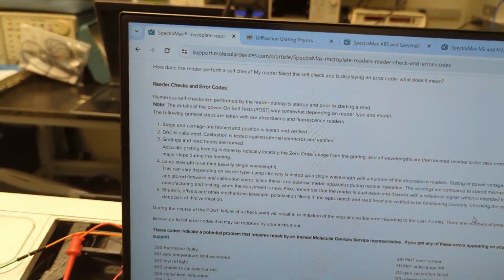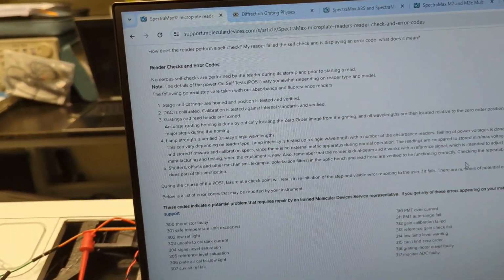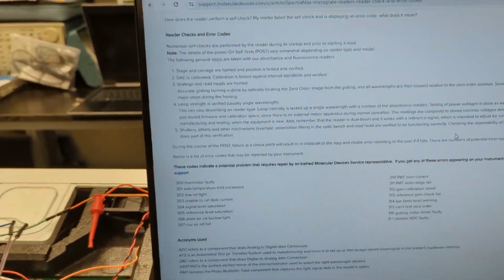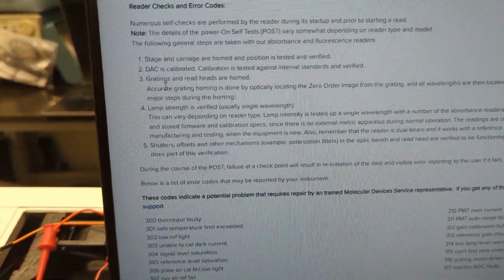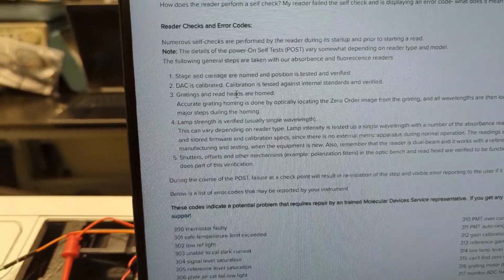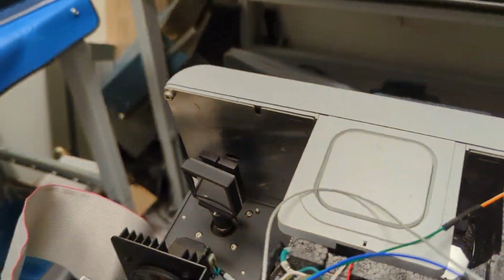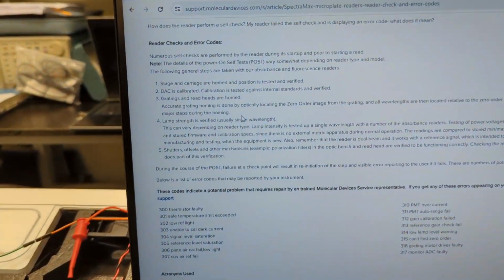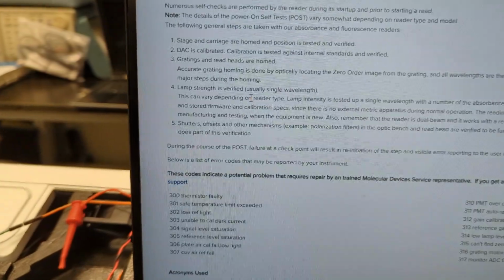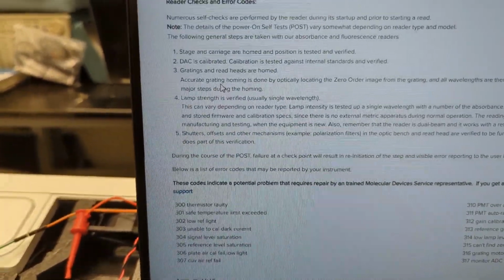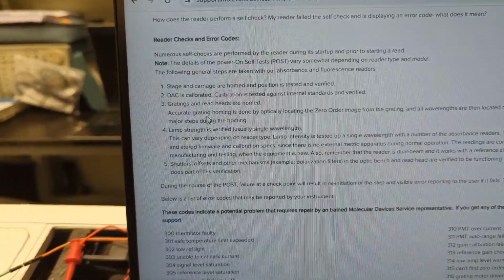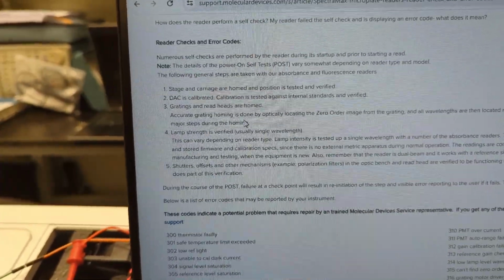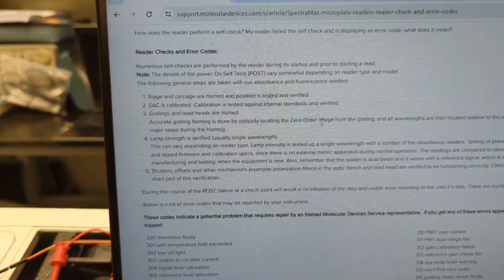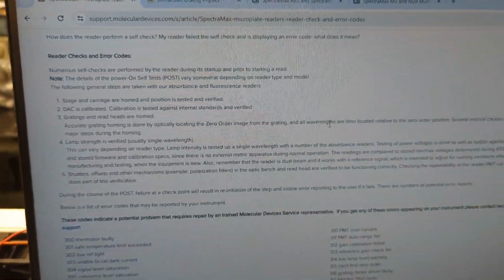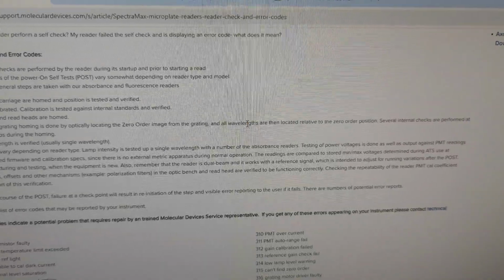Sorry about that. That plate carriage, the drawer will open, it'll close, and then it says the DAC is calibrated, gratings and read heads are homed. So again, that diffraction grating has a homing sensor, so it'll spin that around to home that. Lamp strength is verified, and then this is important. This step right here. Accurate grating homing is done by optically locating the zero order from the grating, and then all wavelengths are located relative to the zero order position.